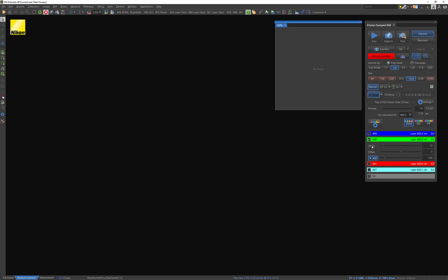Both the gain, HVG here, and the 488, this laser power, are going to give you the two highest bang for your buck settings. This gain here refers to the detector gain. So you can think of this as it detects more photons at the end of the optical pathway. So this works sort of on the other end of the imaging experiment, where you can bump up artificially the signal that you're detecting with your photomultiplier tubes.